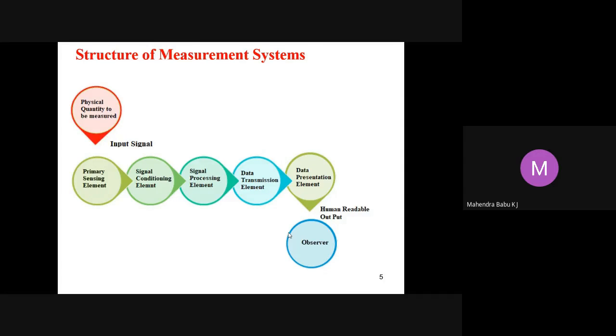For example, an amplifier which amplifies millivolts into volts, or an oscillator which converts impedance changes into variable frequency voltages. And another element is the signal processing element. This element takes the output coming out of the conditioning element and converts it into a form more suitable for presentation. For example, an analog to digital converter, which converts a voltage into a digital form for input to a computer. Or a computer which calculates the measured value of a variable from the incoming digital data. Typical calculations are like computation of the total mass of a product gas from flow rate and density data.